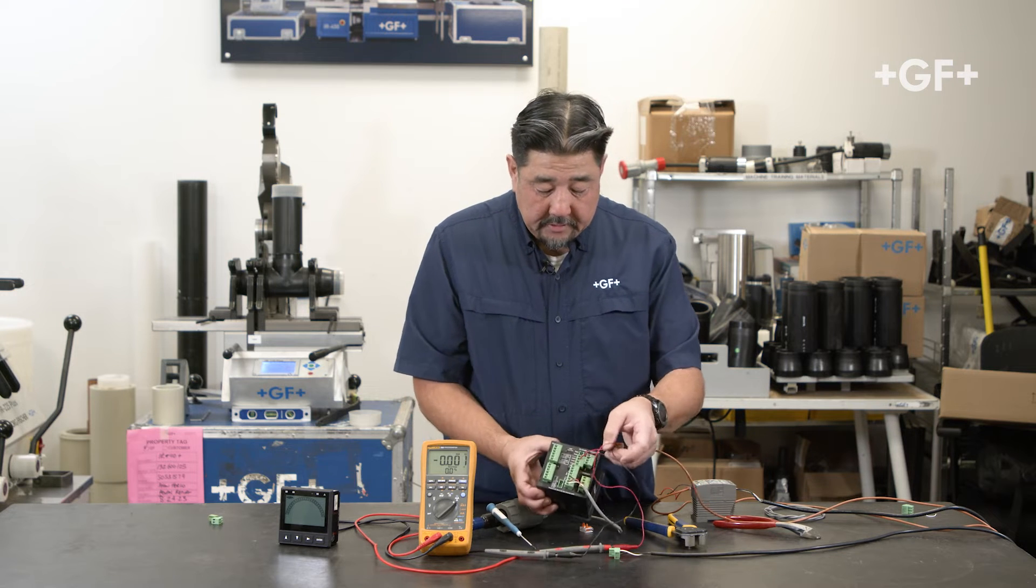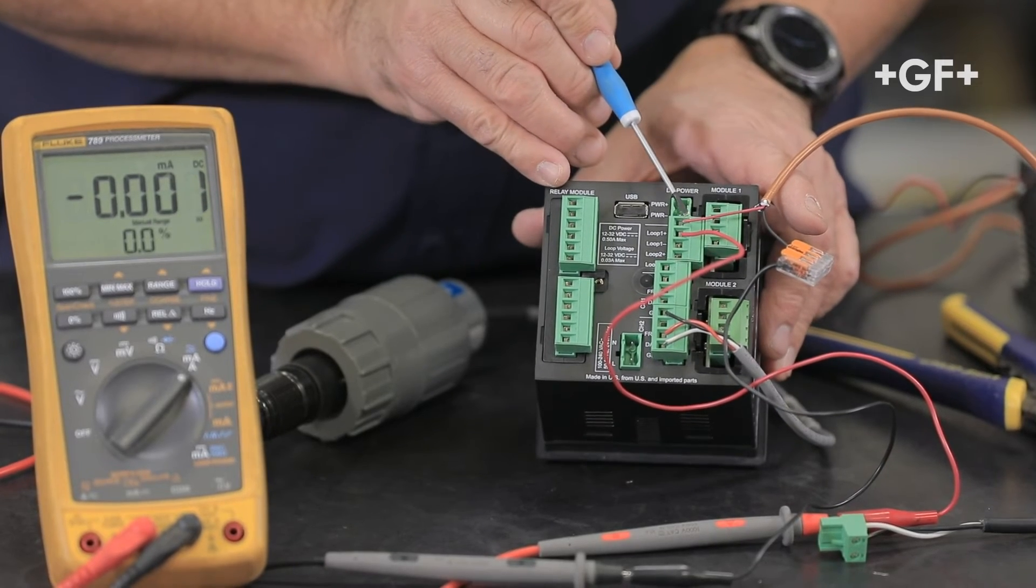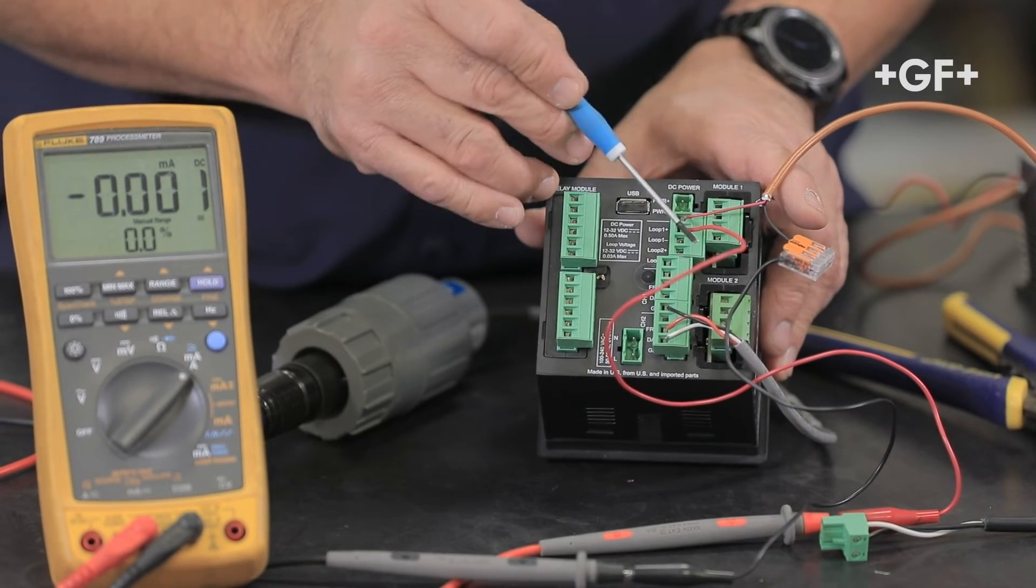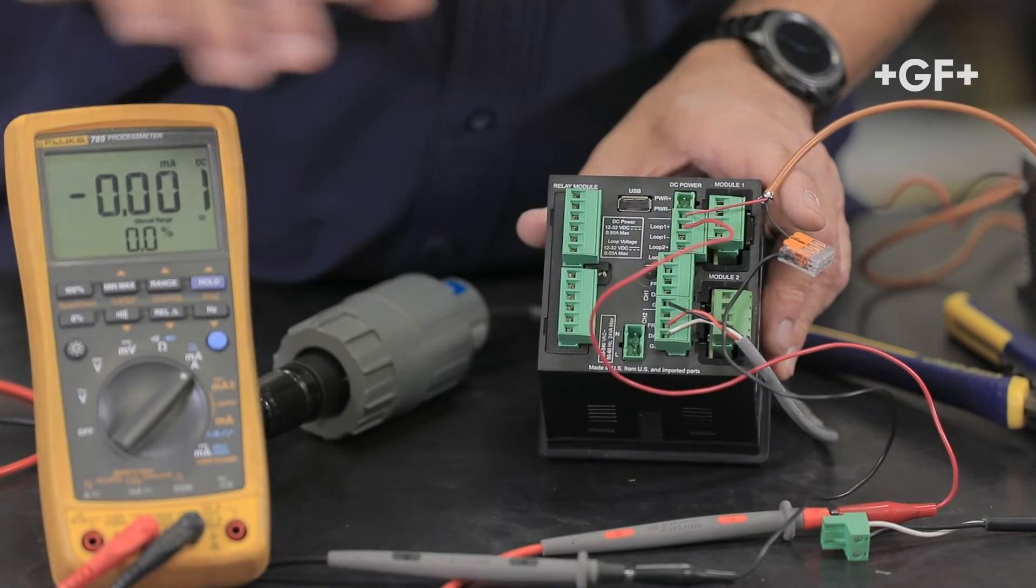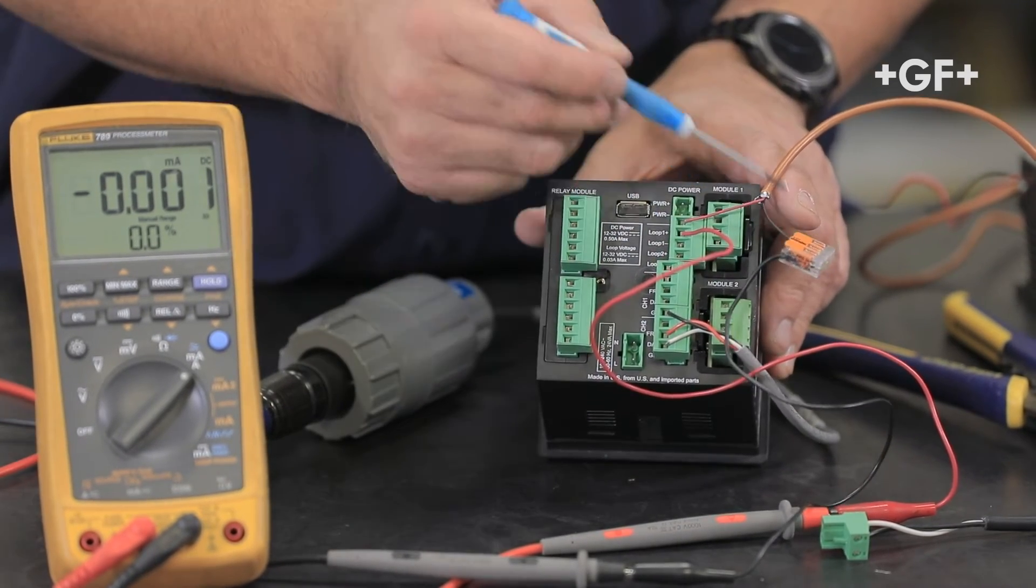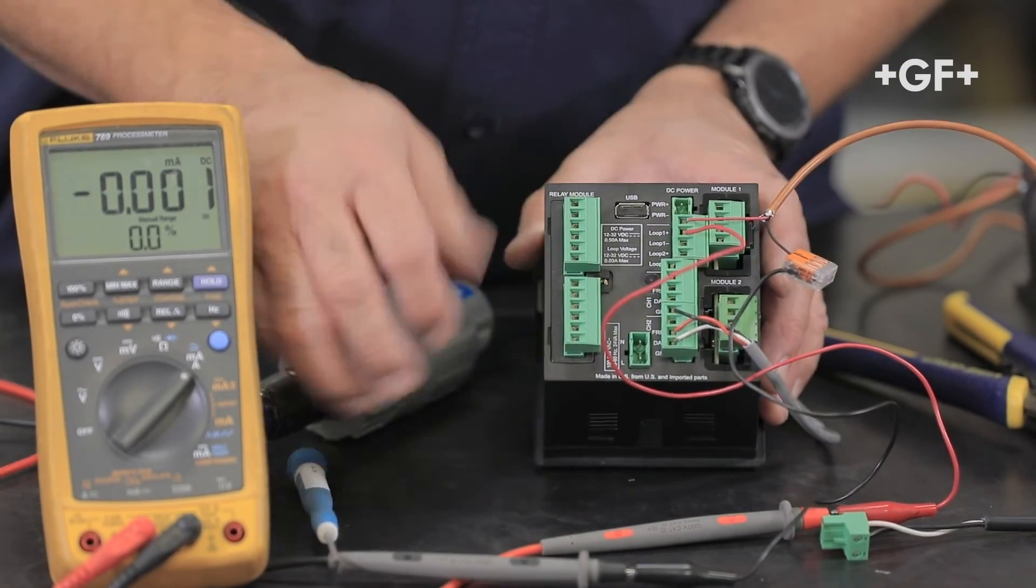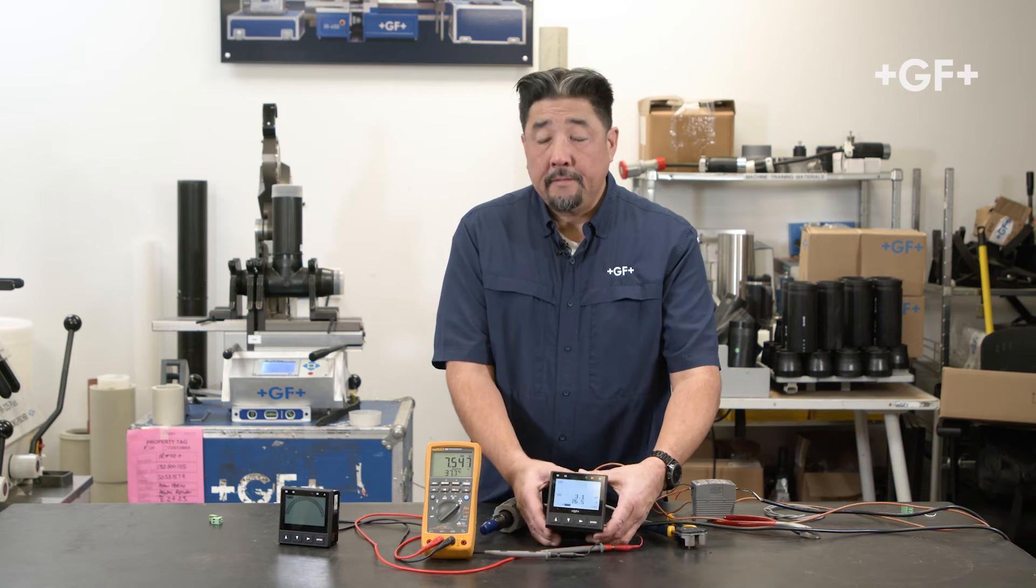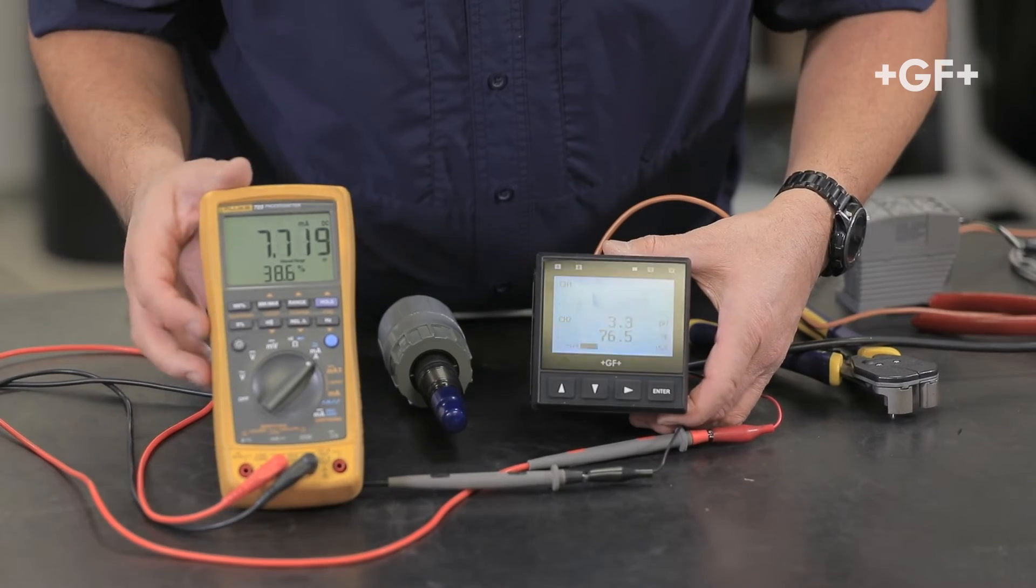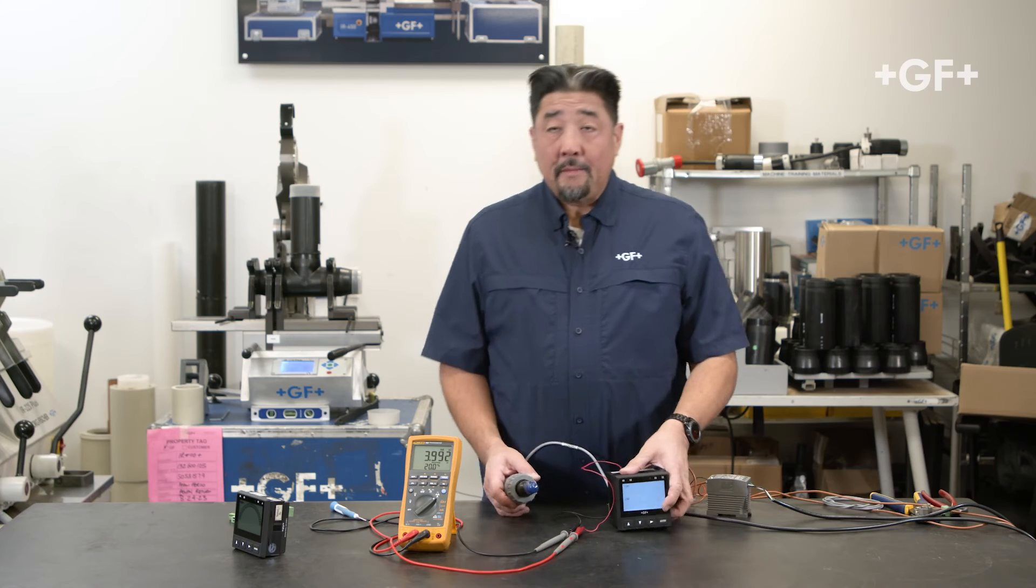So let's go ahead and give that a test. It'll look like this: plus 24 volts in, my signal wire going to the 4 to 20 milliamp device, and my ground to my ground. Let's go ahead and power this up, and here we have 3 pH and a corresponding milliamp value on my meter. So I have wired in a pH sensor.